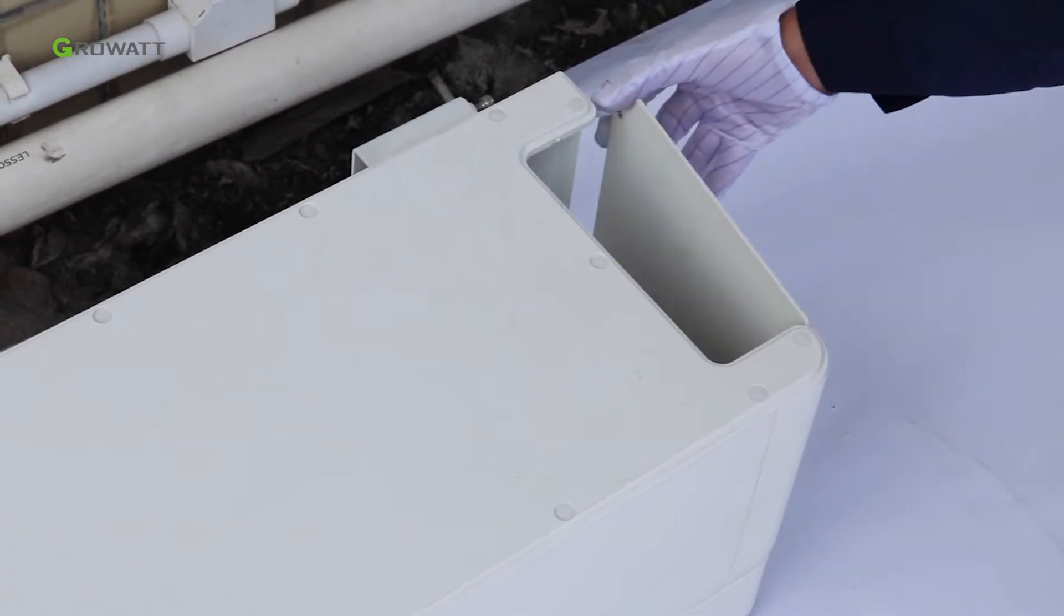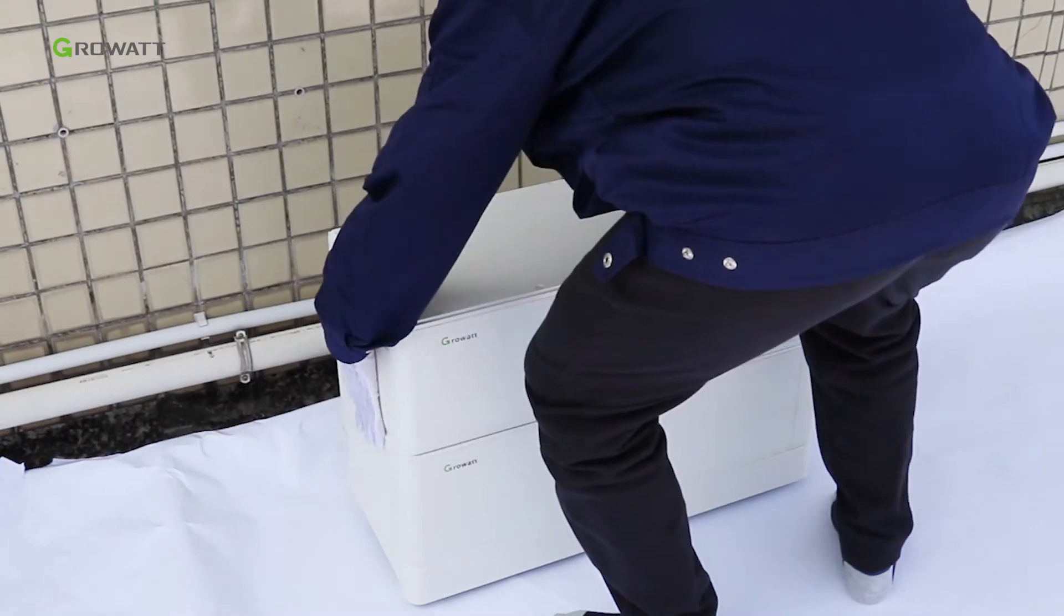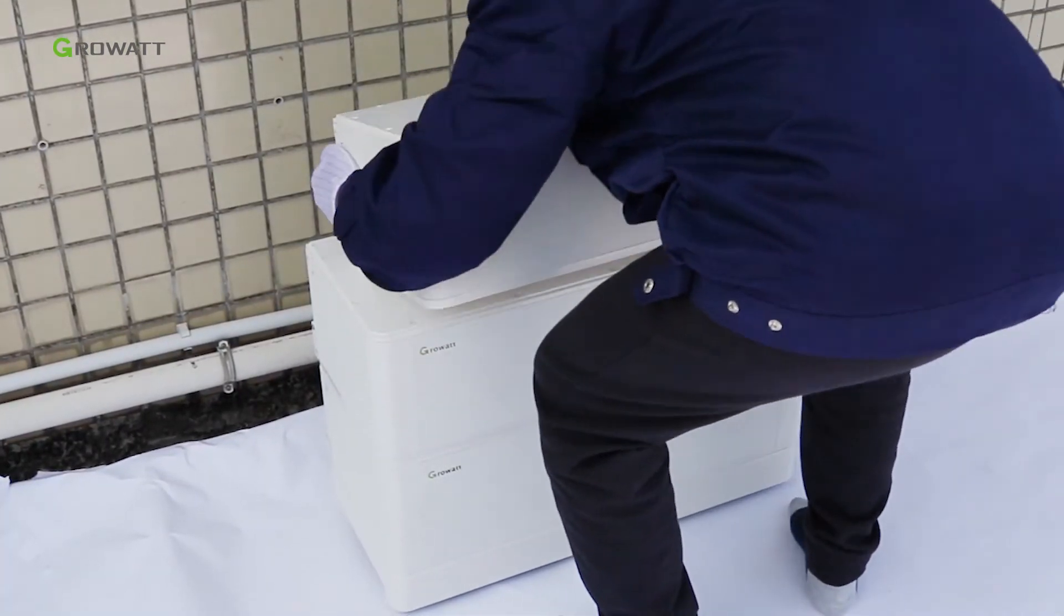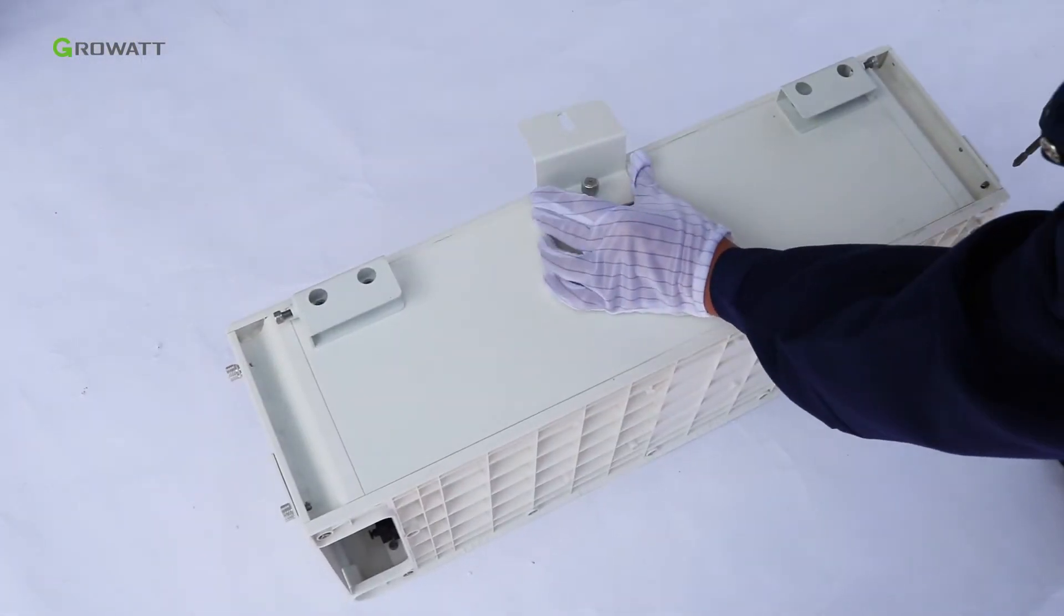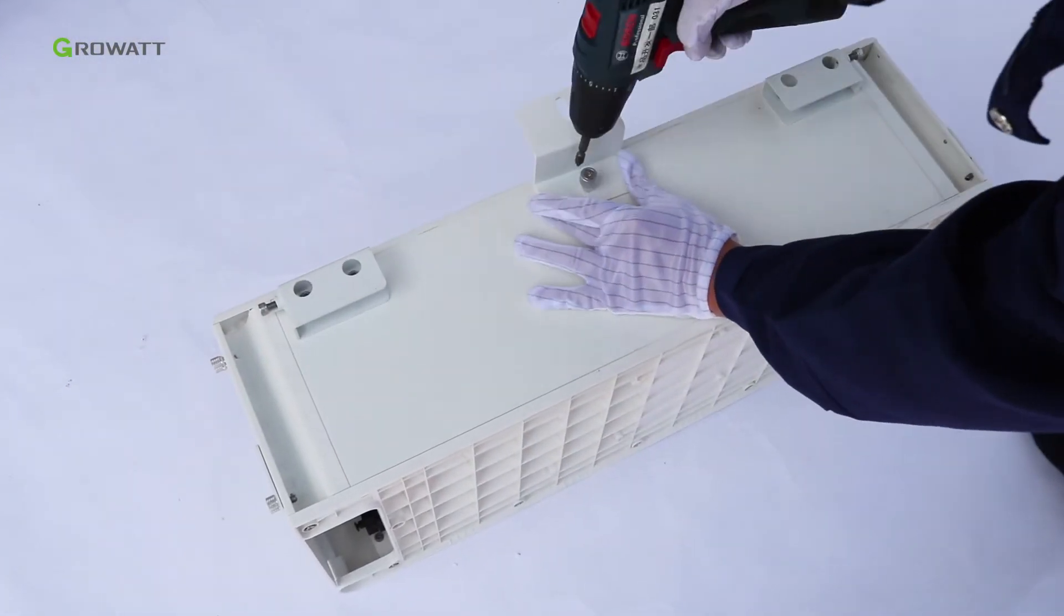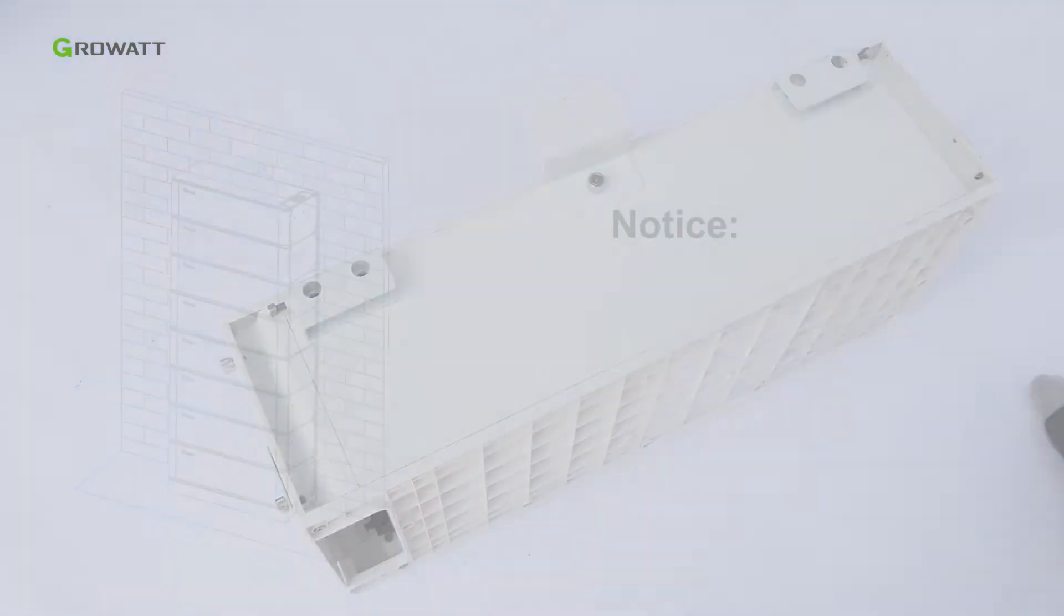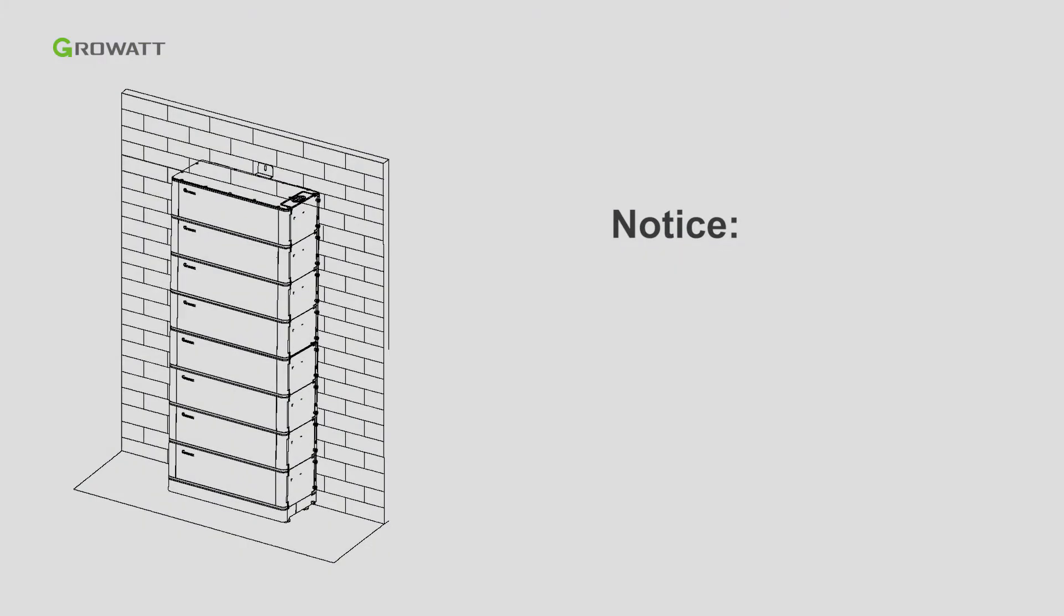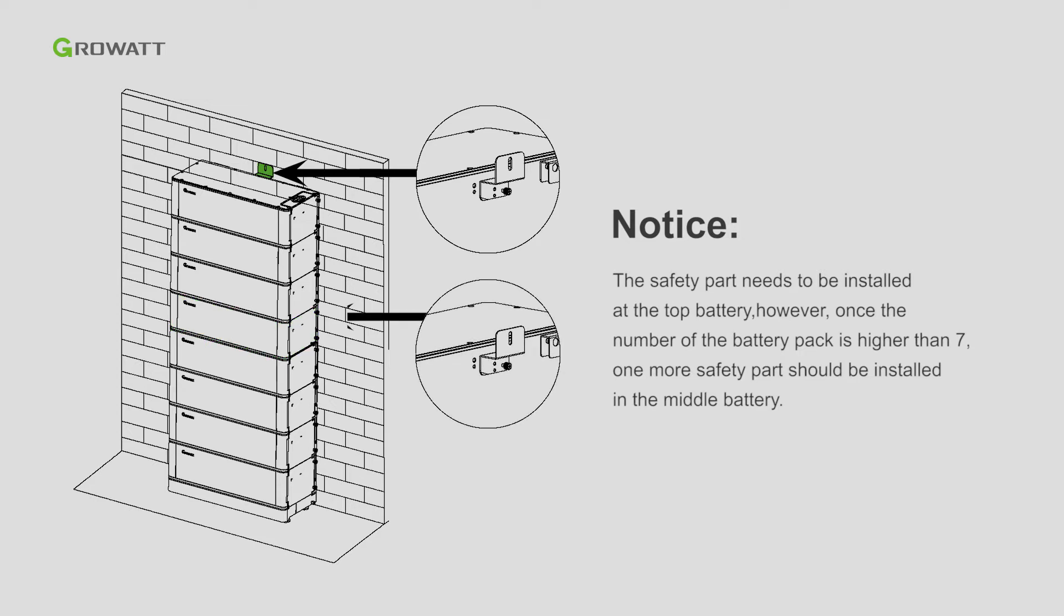Stack the second and third ARK battery pack. Install the safety part in the final ARK battery pack. Notice: the safety part needs to be installed at the top battery. However, once the number of battery packs is higher than seven, one more safety part should be installed in the middle battery.